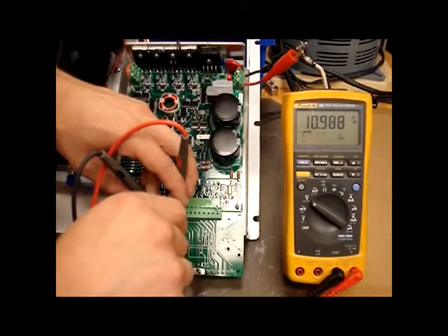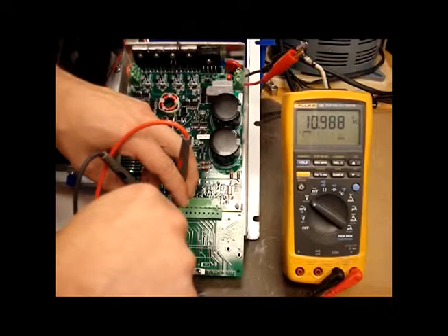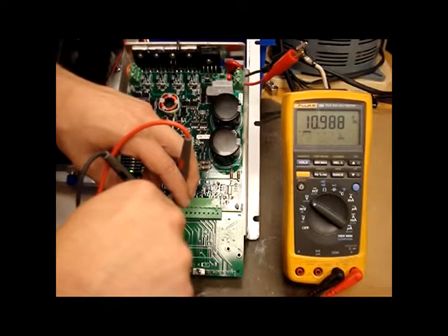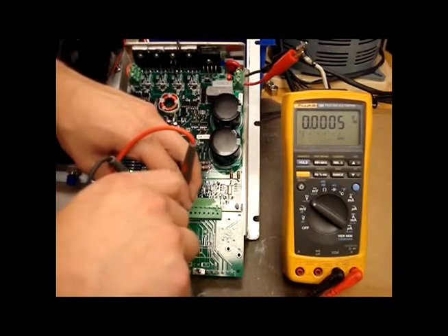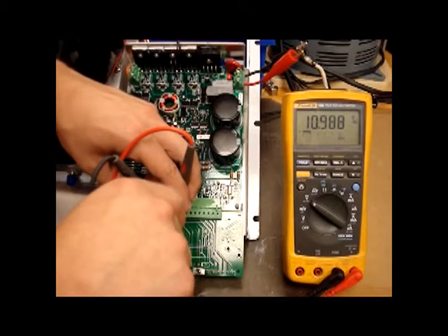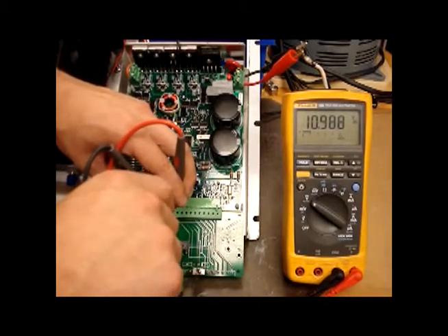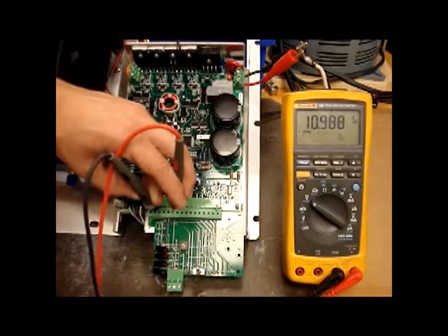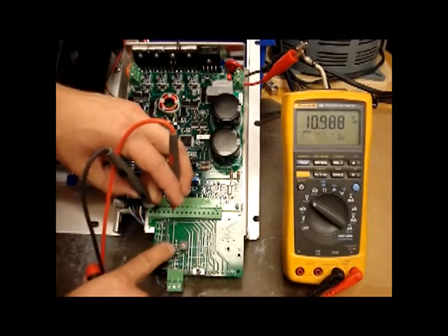We're going to go 0 to 100% PDM on this potentiometer. We're at least at 10 volts, so that's 100%. We're going to come down to 0%. We're reading about 0 volts. That is correct. If there is no movement on that with external PDM, the signal is incorrect, and something needs to be checked, most likely with the PLC.